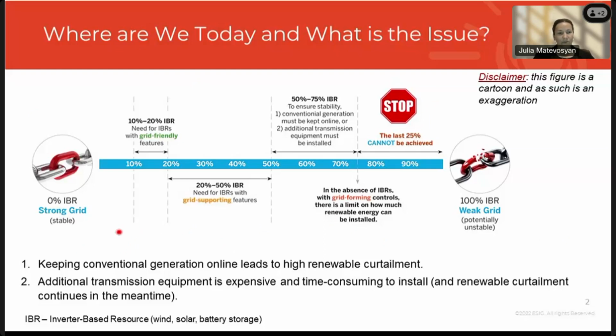timeline, we started with just very few inverters. There were very few requirements applied to those. Basically, they were supposed to get out as soon as something happened on the grid and not be in the way. As we progressed towards maybe 10-20%, it was no longer acceptable, and requirements such as ride-through got introduced, ride-through voltage, ride-through frequency events, and so resources stay connected.